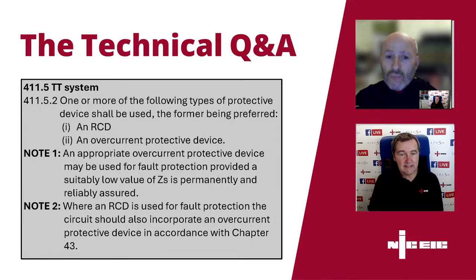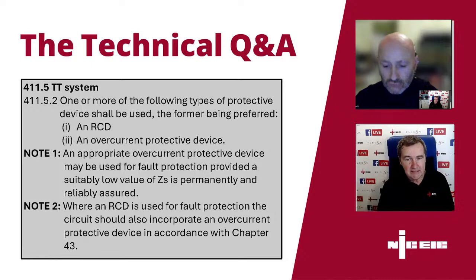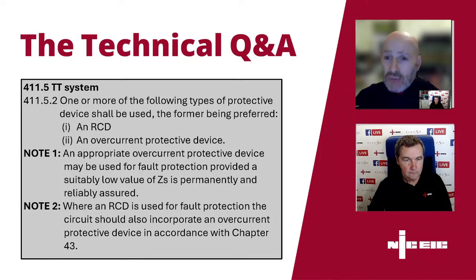So I guess the key words in what you said is it's a suitably low ZS which is permanently and reliably assured. That's the key bit. Just one more piece of information from that particular regulation: where an overcurrent protective device is used for fault protection, the circuit also needs to incorporate an RCD for additional protection in accordance with Chapter 43 - sorry, the circuit still needs to provide a means of overcurrent protection, it's not just the RCD alone.